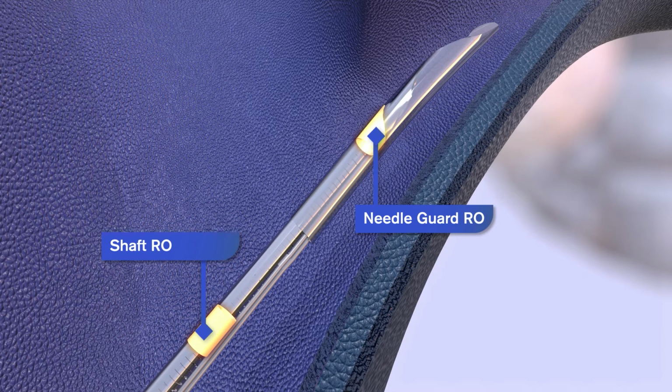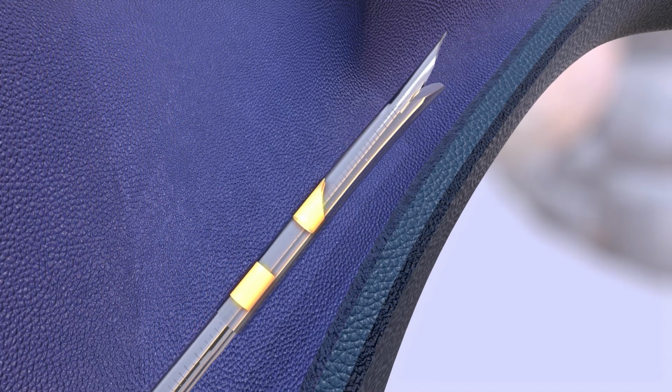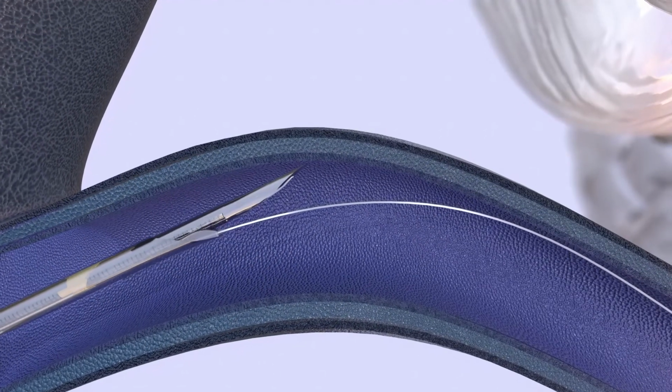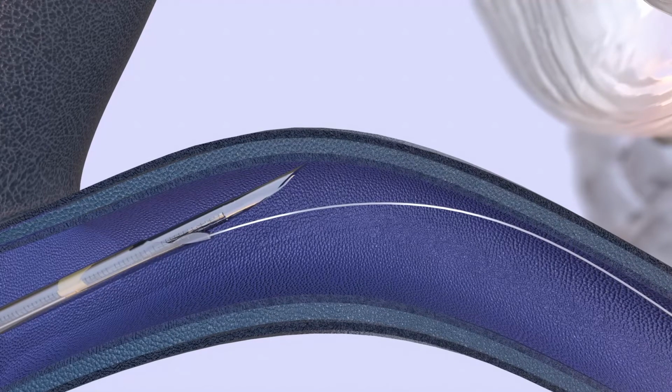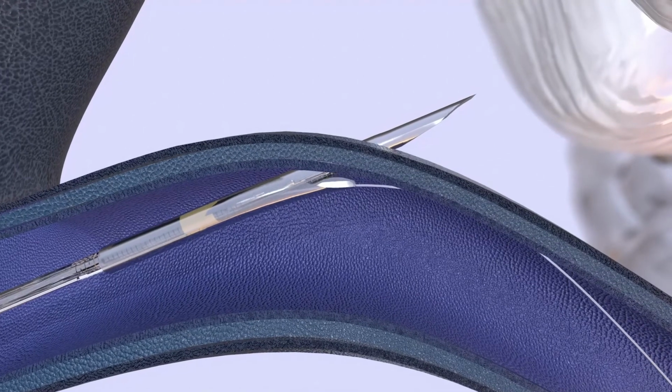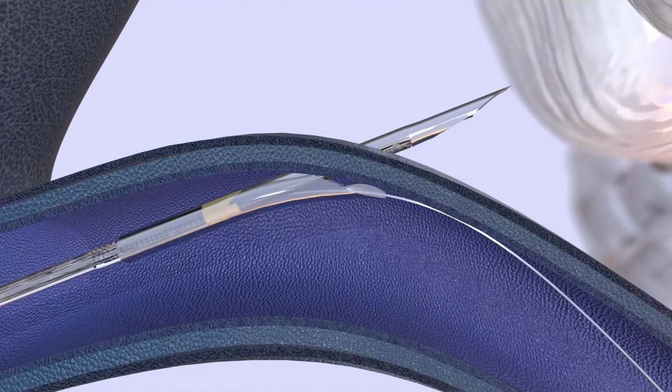The operator will then retract the needle guard to expose the needle, using a knob on the delivery catheter handle. When the two RO markers converge, the needle guard is fully retracted and the needle is exposed.